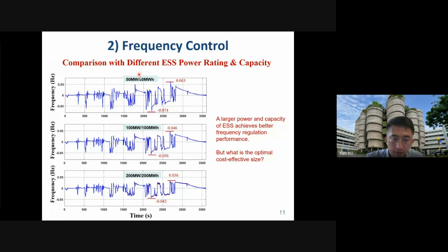We compare 50 megawatt hour, 100 megawatt hour, and 200 megawatt hour capacities of the energy storage system. You can see clearly that as the size increases, the frequency maximum deviation and fluctuation magnitude continuously decrease. However, we need to balance total cost against total effectiveness, so we perform a cost-effectiveness analysis.